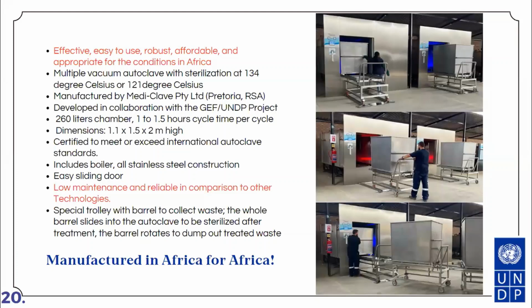The waste units installed during the Ebola crisis were 260 litre chambers with a cycle time of about one to one and a half hours. They are certified to meet or exceed international autoclave standards, and include an on-steam boiler with all stainless steel construction. It also has an easy sliding door, is low maintenance and reliable, and has a special trolley with a barrel to collect waste. The barrel slides into the autoclave to be sterilized, then rotates to dump out the treated waste.